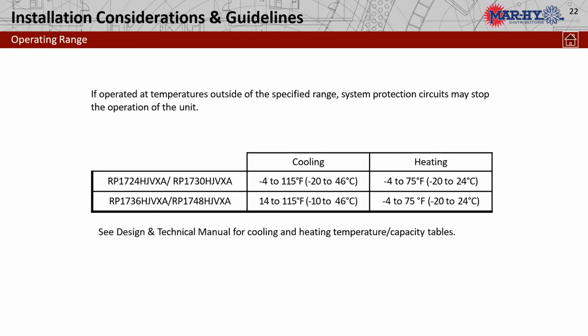The operating range. So the 2 and 2.5 will cool from -4 to 115 degrees. And in heating, it's good from -4 to 75 degrees. Now the 3 and 4-ton goes down to 14 degrees in the cooling mode up to 115, and in the heating mode, -4 to 75 degrees. Pretty good range. And what does that tell you about the cooling? It's already got the built-in low ambient. If we can cool down to 14, we're low ambient.